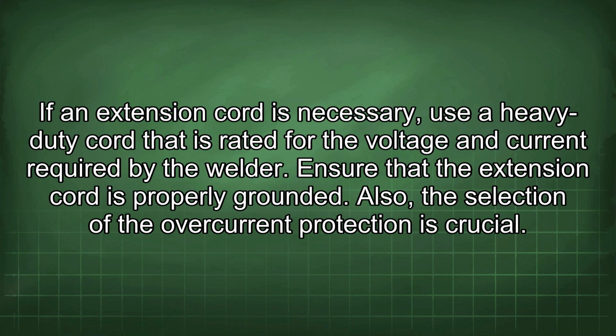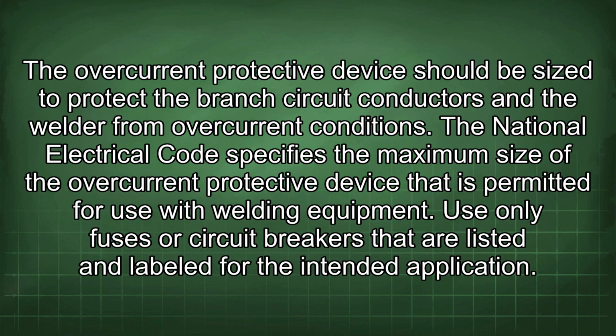Also, the selection of the overcurrent protection is crucial. The overcurrent protective device should be sized to protect the branch circuit conductors and the welder from overcurrent conditions. The National Electrical Code specifies the maximum size of the overcurrent protective device that is permitted for use with welding equipment. Use only fuses or circuit breakers that are listed and labeled for the intended application.